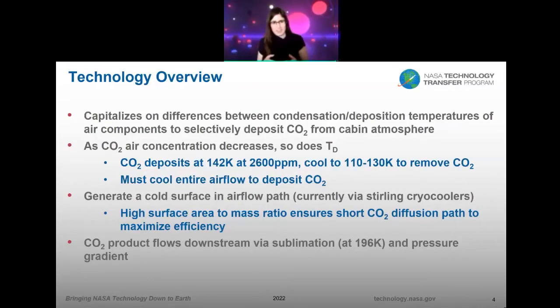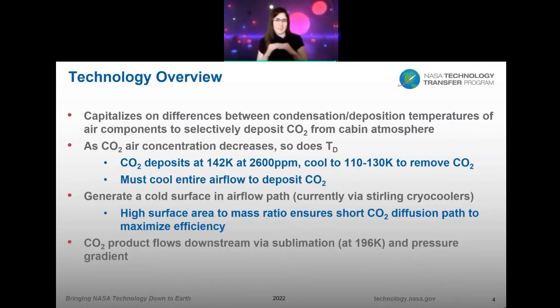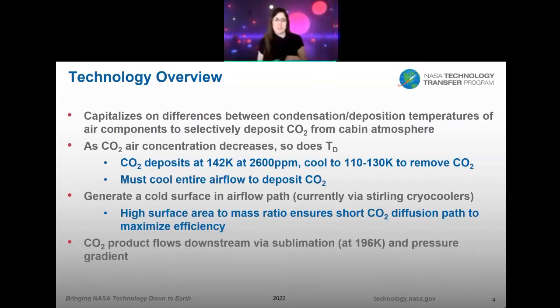So how does CDEP actually work? It capitalizes on the differences in condensation or deposition temperatures of air components to selectively deposit CO2 from cabin atmosphere. As you cool down air, you first either liquefy or freeze out water depending on humidity concentration levels, and then you deposit out CO2 because of the phase diagram. If you go even colder, you would start to liquefy oxygen. But as long as you don't go that cold, you are selectively depositing CO2. However, the concentration of CO2 in the atmosphere dictates how cold you actually need to go. As CO2 air concentration decreases, so does the deposition temperature. For example, at the spacecraft concentration of 2 torr or 2600 ppm, it would start to deposit at 142 kelvin. To actually remove gross amounts of CO2 from the atmosphere, we have to cool further to about 110 to 130 kelvin. And since we have to cool the entire airflow to deposit out that CO2, we can't avoid cooling all the air.